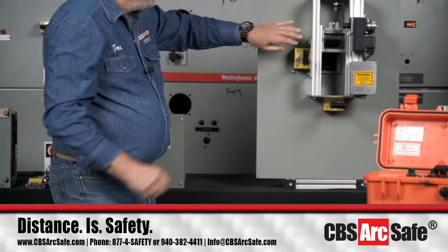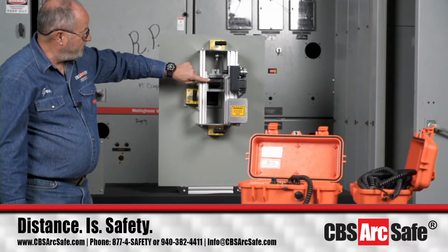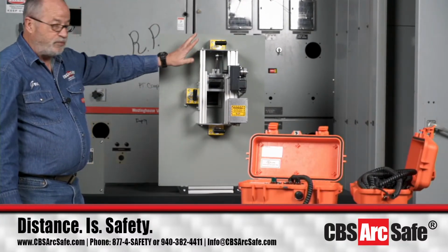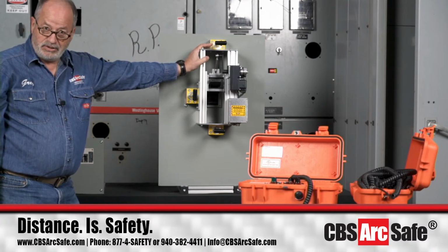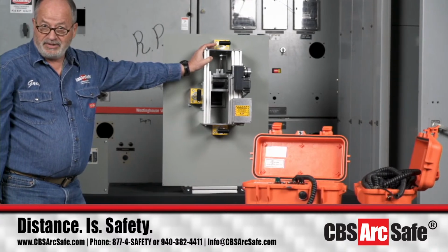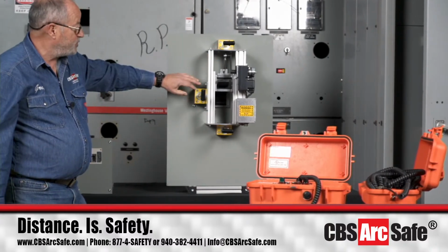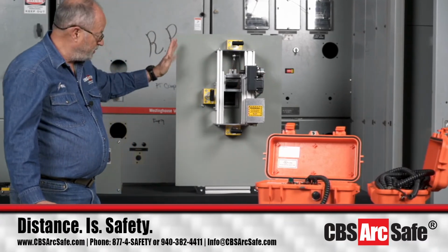All right, our next one. If you can close in here, Brian, where my finger's at, you can see that we've got the handle extension on this one. We do make a version of the RSA so that it can operate without the handle extension, if that's how you want to do it, but a lot of our customers like to leave the handle extension on. So we've set this one up so we've got clearance over on this side for lockout, tag out, just built into it.